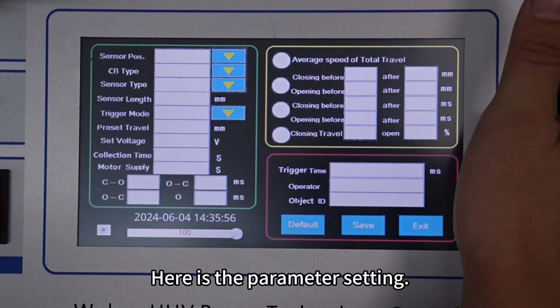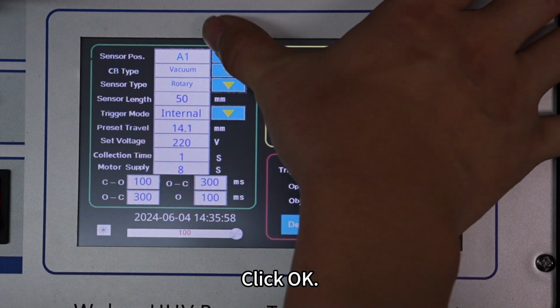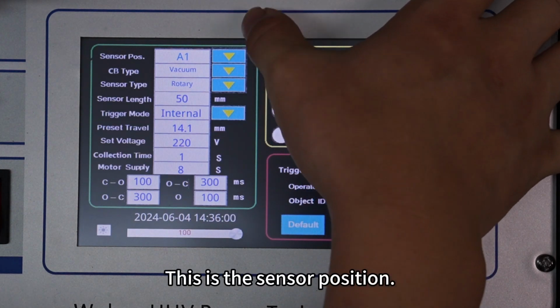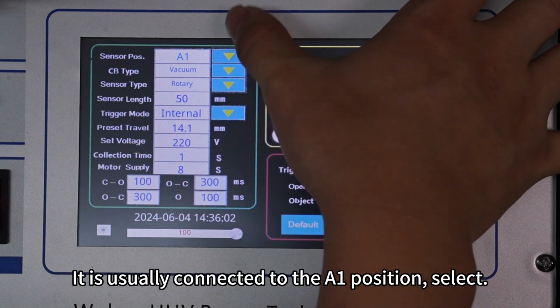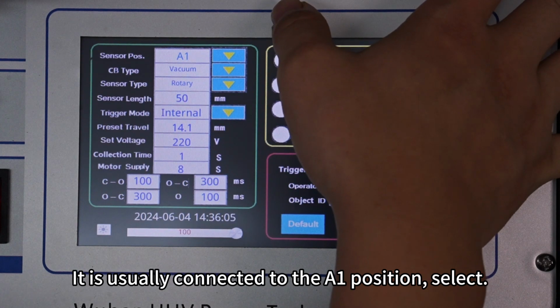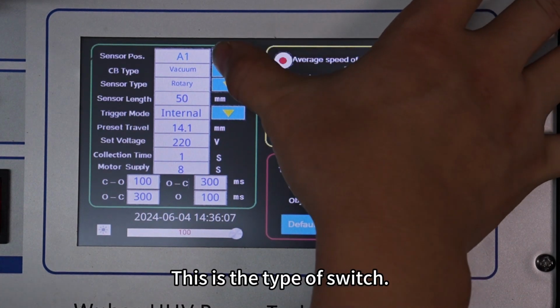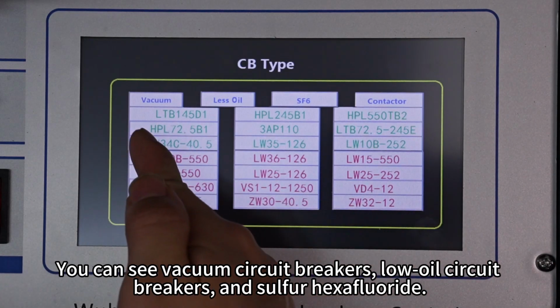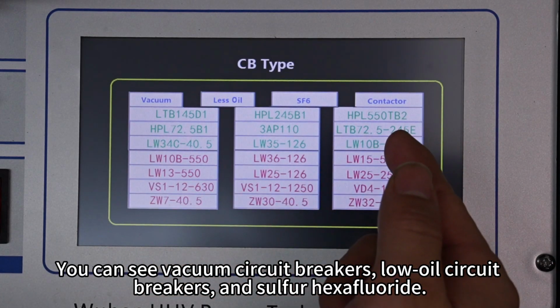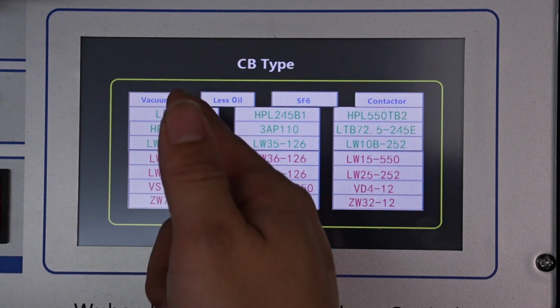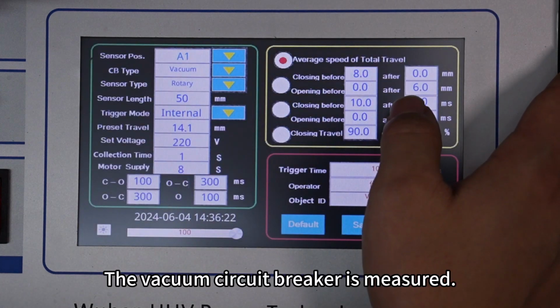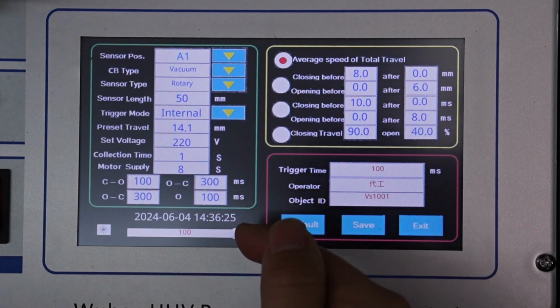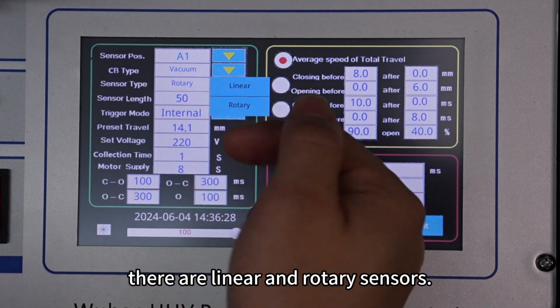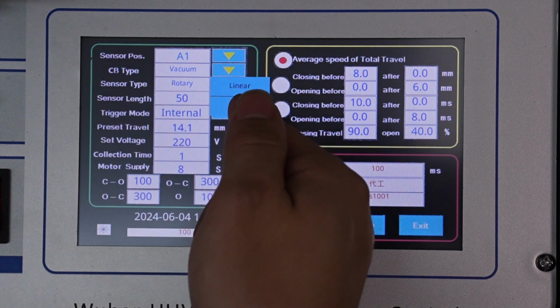Here is the parameter setting. Click OK. Enter the page. This is the sensor position. It is usually connected to the A1 position. Select. This is the type of switch. You can see vacuum circuit breakers, low oil circuit breakers, and sulfur hexafluoride, and its contactor. This is its model. The vacuum circuit breaker is measured. This is its sensor type. There are linear and rotary sensors. Now the rotary sensor is used.